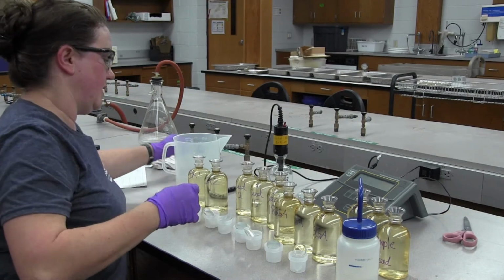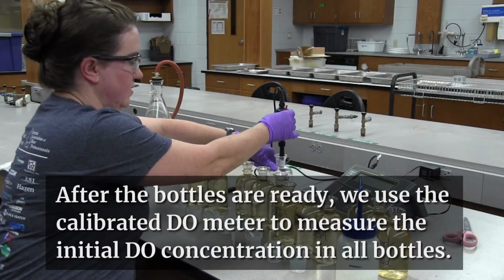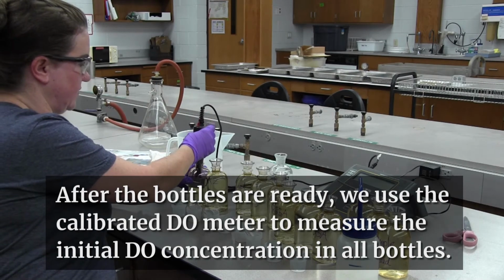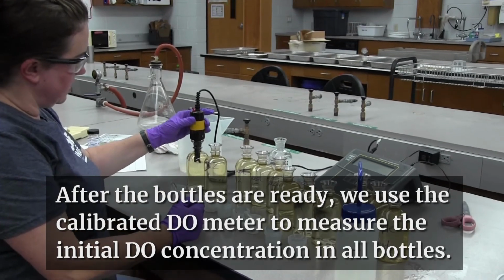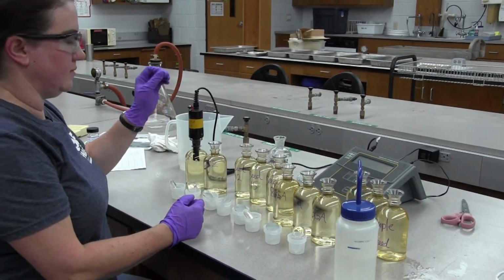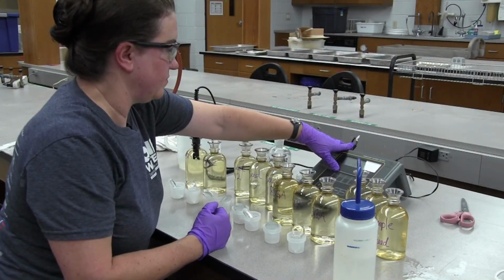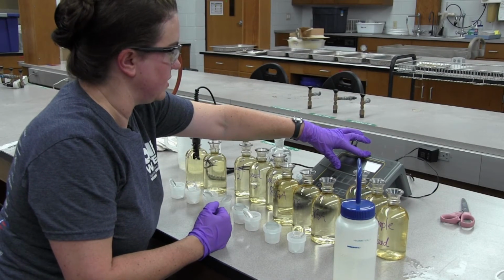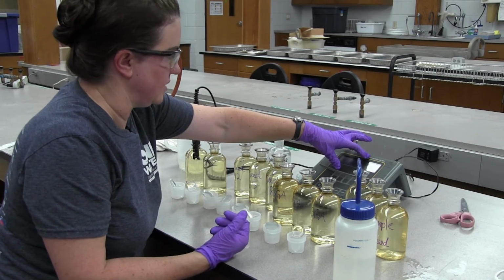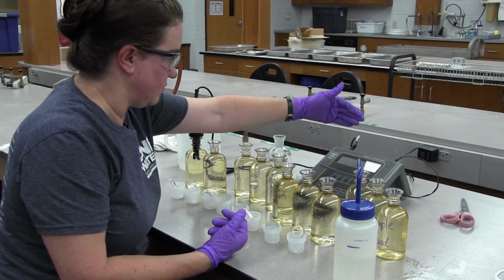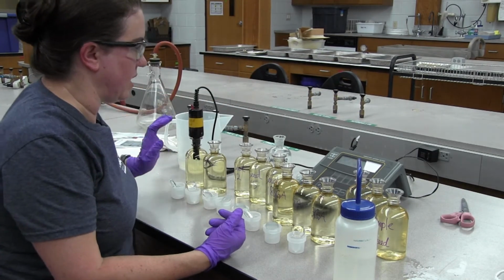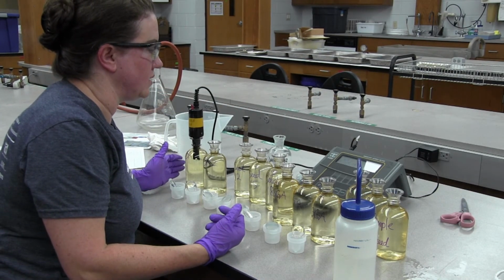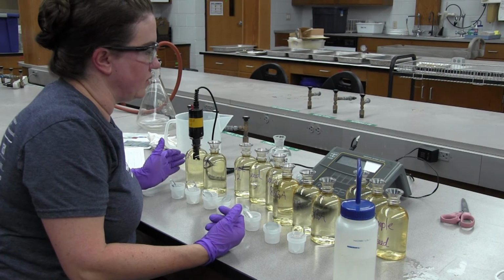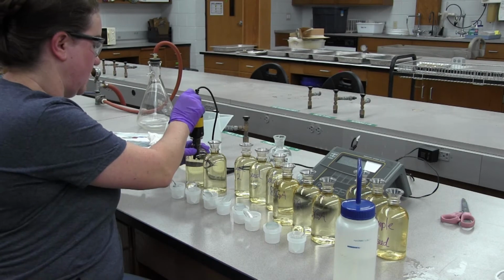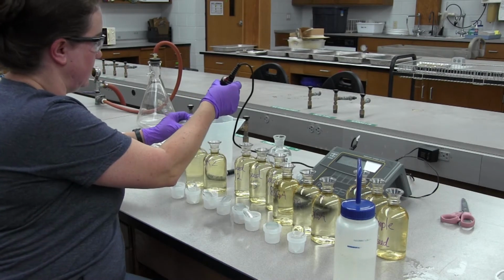Okay, now we're ready to read. I'm going to read our blanks first. So when you put the probe in the bottle, turn the stirrer on, and the DO is stabilized. In the case of this meter, the number will stop and there'll be an asterisk popped up beside the milligram per liter units. So this is 8.45. Now I'm going to read the next sample.